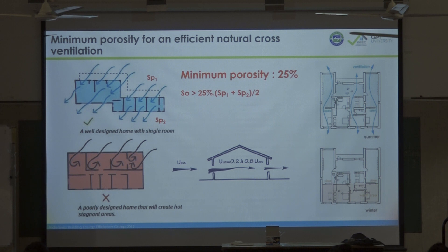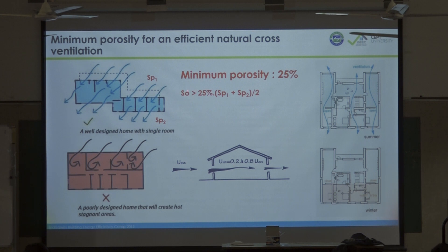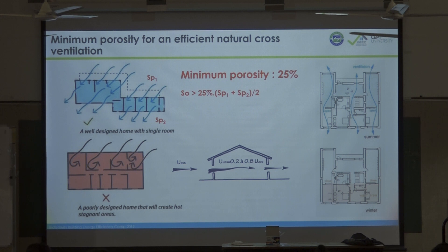When you design a building, you have to check that the air can go from one facade to the opposite one — this is what we call a cross-ventilated building. In each case you need 25 percent porosity on facade one and 25 percent on facade two. The surface of openings must be above 25 percent of the mean of the two facades. For a rectangular building sp1 and sp2 are equal; for different shapes, calculate the mean of the two facades and take 25 percent.